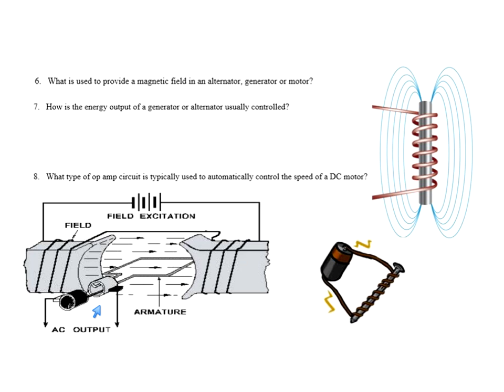The interesting thing is that when you generate AC, it's the speed of the rotor that determines the frequency. A 60 hertz signal has to be rotated 60 times per second, three-phase. It can be rotated slower, but we're not going to get into that. So you can't change the speed — the way you control the output of the generator is by controlling the strength of the field with different current in the field.